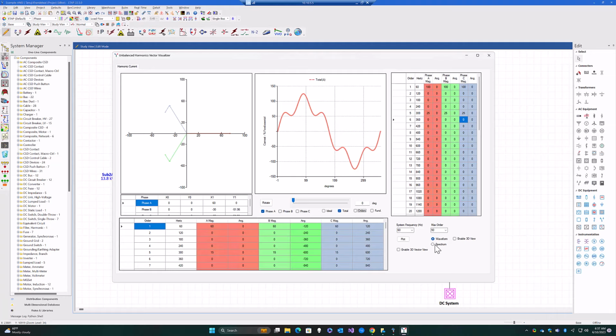And for this time domain signal, we can see the corresponding spectrum as well. And as the amount of harmonics are increased in the system, let's say we have something further on the seventh harmonic as well, we can see there's further distortion of the waveform, and an additional seventh order spectrum that appears in our waveform on the right hand side. And then as we move our vectors along, we can see very clearly how the unbalanced vectors remain the same, 120 degrees apart, but the corresponding vectors for the harmonics are also recomputed, and they vary quite substantially as the amount of unbalance in the system will also increase later on.